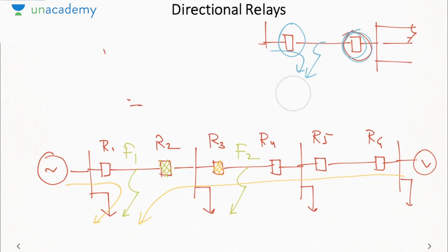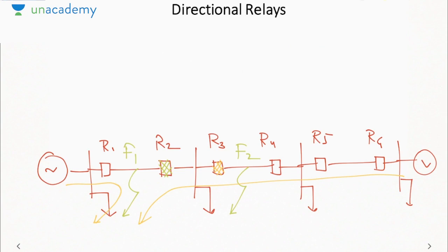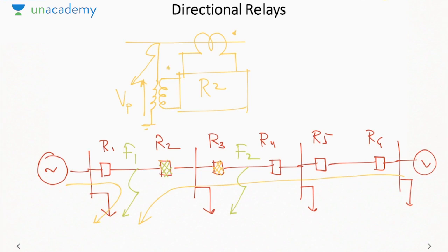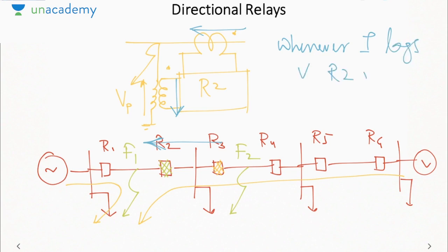So let me show you how we design a relay. Now when we design a relay at R2, so the fault is here. So first we will use a current transformer. Then this will feed a relay R2, and here we will have a potential coil which will measure the voltage of the fault point. Let me call it VP. Now as you can see, when the current is entering here, the current in this will be like this. So this current will be lagging the voltage, because when fault is occurring here, as I told you, fault current is always lagging power factor. In such a case, relay R2 must operate. That means whenever current lags, relay R2 must operate.